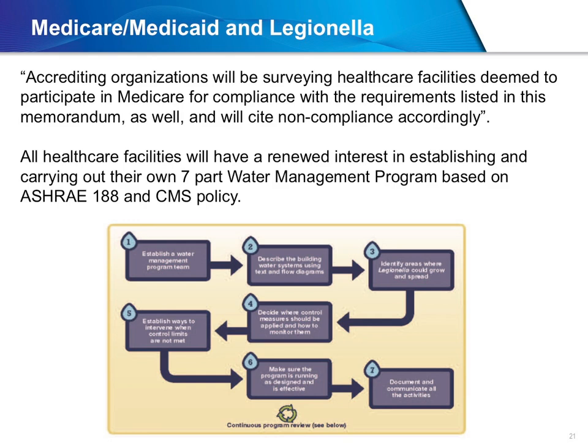Those facilities deemed unable to demonstrate measures to minimize the risk of LD are at risk of citation for noncompliance with the CMS conditions of participation. The CMS policy memorandum indicates clearly that accrediting organizations will be surveying healthcare facilities deemed to participate in Medicare for compliance with the requirements listed in this memorandum, as well, and will cite noncompliance accordingly. Based on this, it is expected that all healthcare facilities will have a renewed interest in establishing and carrying out a full water management program based on ASHRAE 188 and the CMS policy.